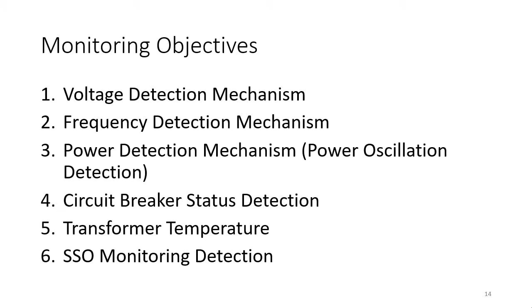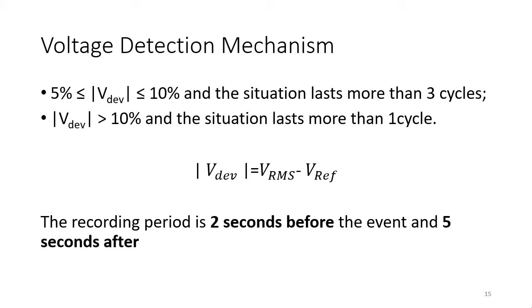So our system will detect if the voltage deviation is between 5% to 10%. If this case lasts more than 3 cycles, our system will start recording. The recording period is 2 seconds before and 5 seconds after. This is how long we record because we want to make sure that if something happens, engineers can see it from beginning to end. And if it's a deviation higher than 10% and lasts more than 1 cycle, it's going to start recording. That's for the voltage detection mechanism.